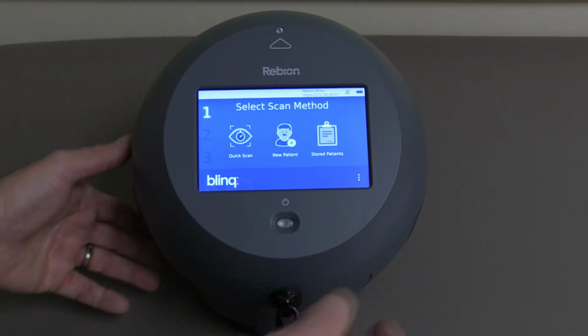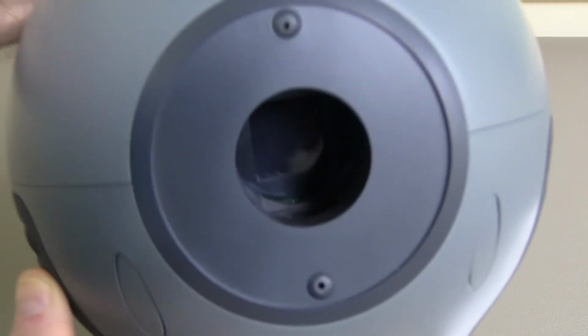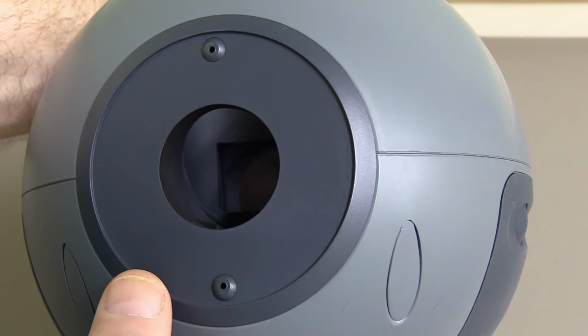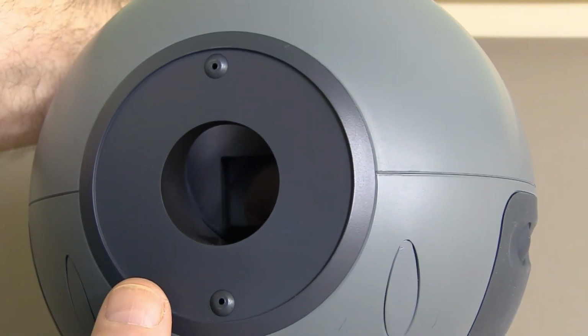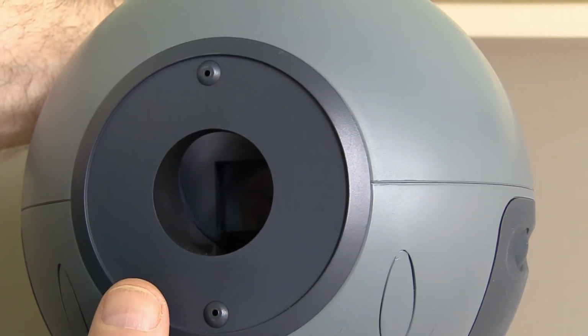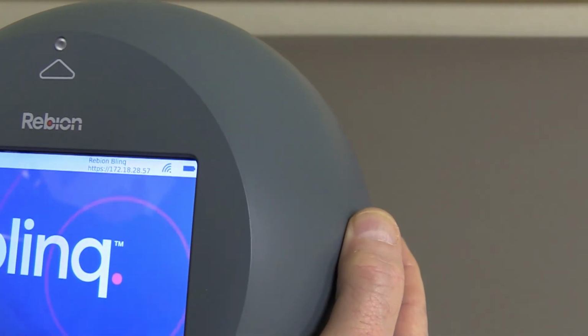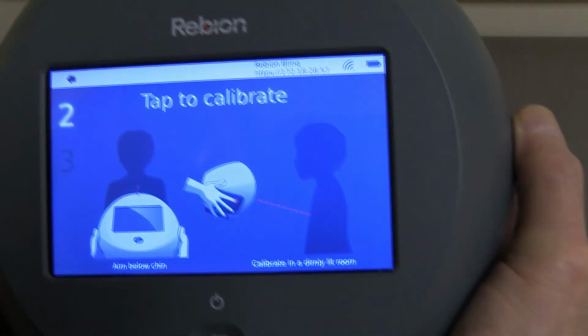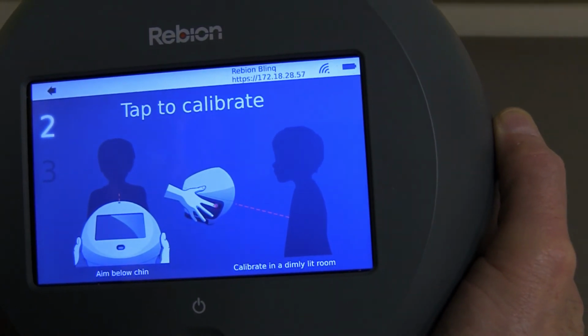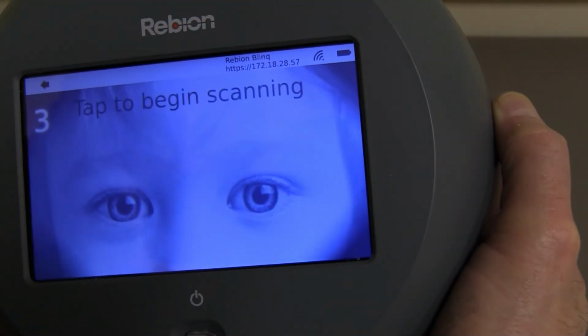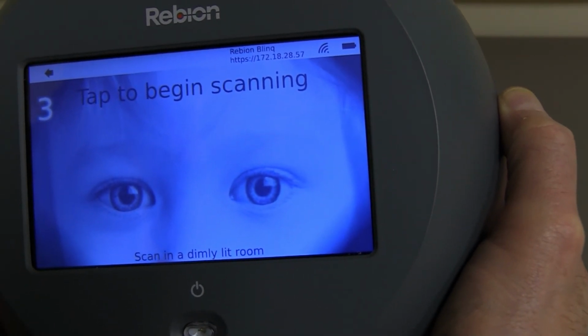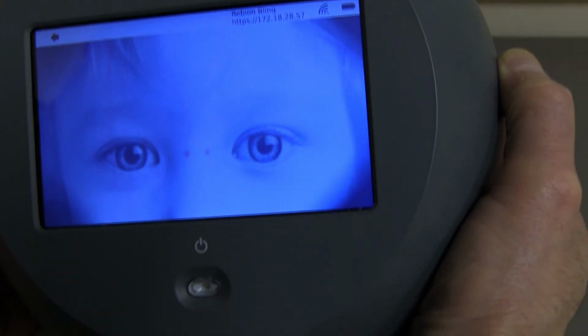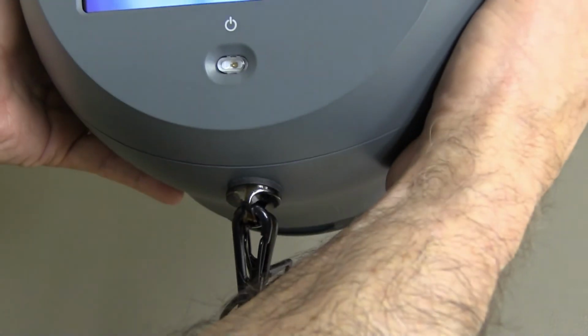So the device is this orb. The child looks at this central opening. When activated, the child will see a face etched into a mirror on the back of this opening. And when the user uses the device, one merely pushes one of either button on the handles, and it goes into what's called calibration mode. As illustrated here, you project the light onto the chest of the patient. It takes about 1/10 of a second. And then, as depicted here, you push the button again, and then you bring the eyes, or the target lights, into alignment with the bridge of the nose.